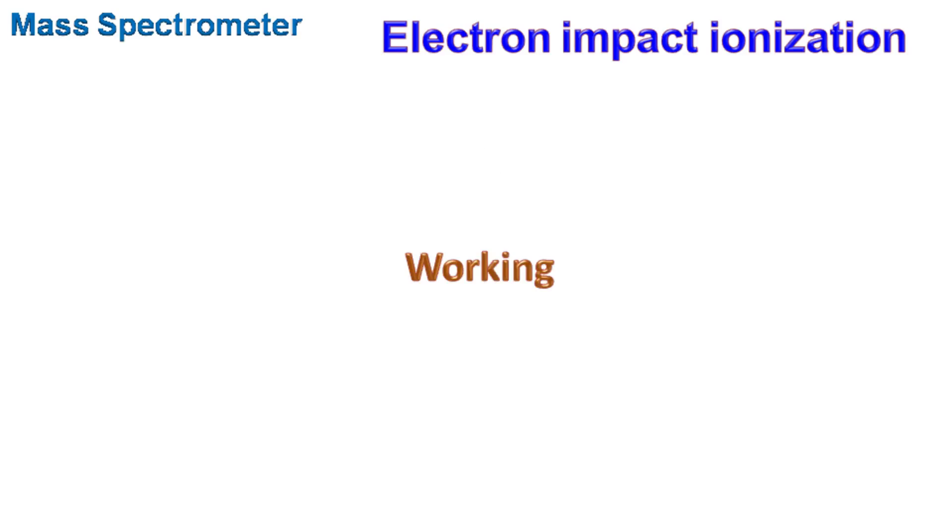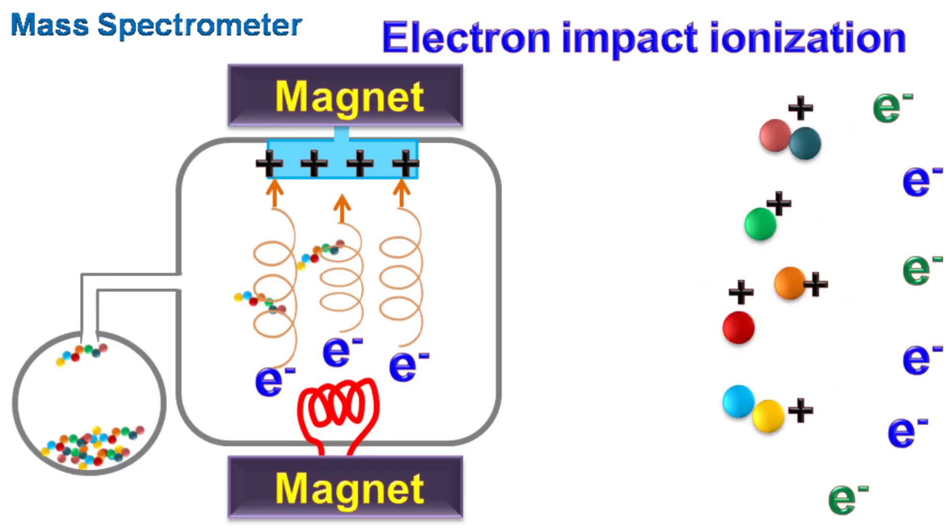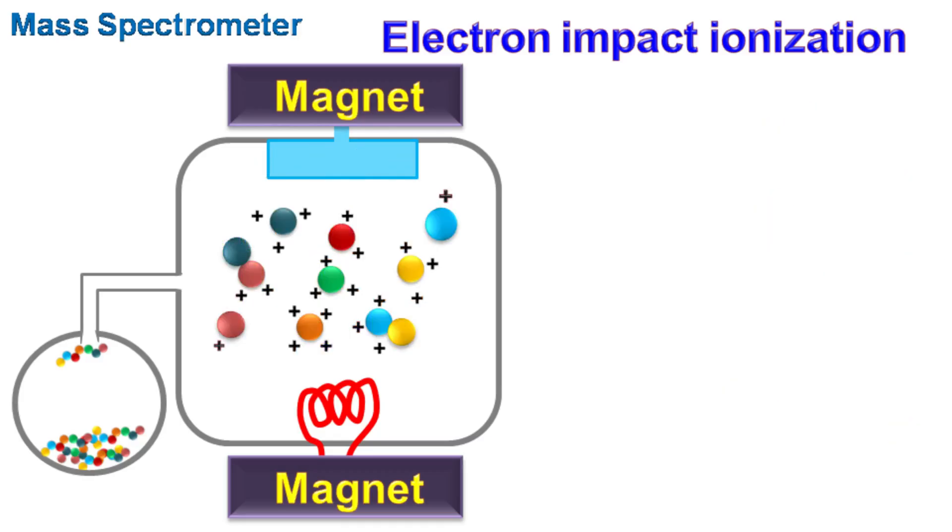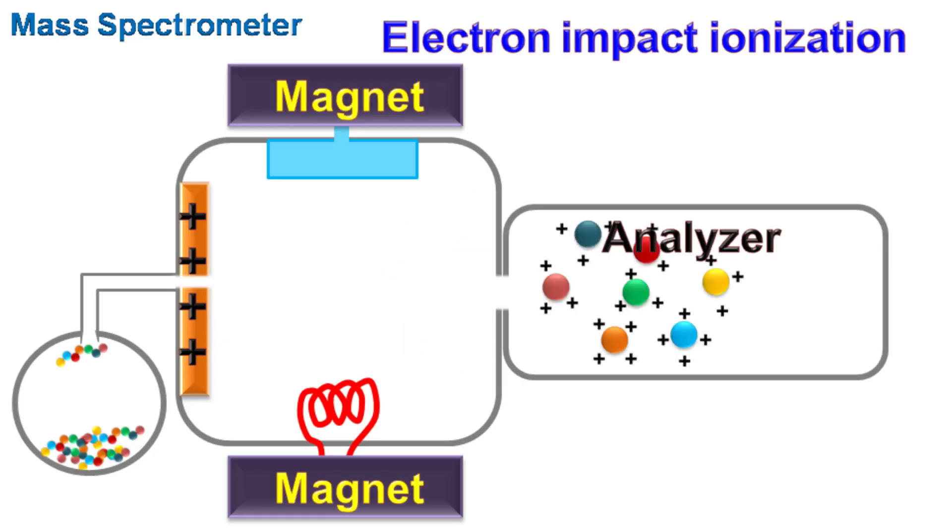Let's see the working of electron impact ionization. The sample is first vaporized and introduced in the ionization chamber through the sample inlet. The high energy electrons collide with the molecule and break it into small molecules, and as the electrons are released, the fragmented molecules will have a positive charge. To analyze these fragmented molecules, there is a repeller electrode which has a positive charge. The repeller electrode repels the positively charged molecular ions and accelerates them so that they can enter the analyzer.